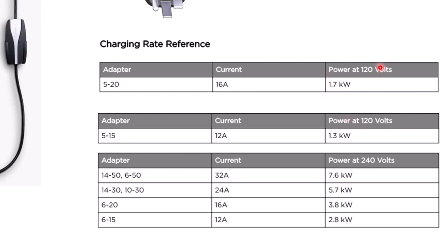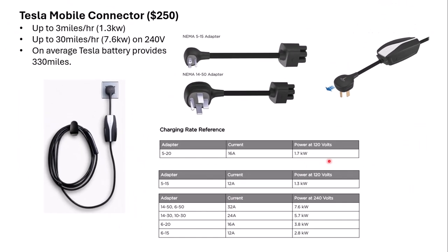So on the lower voltage, they come with 15 or 20 amp, and at the higher voltage, they basically come in 15, 20, 30, or 50 amp. And the currents are basically 80% of this amp rating. So if you have 20, 80% will be 16, and that's how these currents are calculated based on this. But for the 50, 80% would be 40 amps. So in this case, it's a little bit less than 80%.